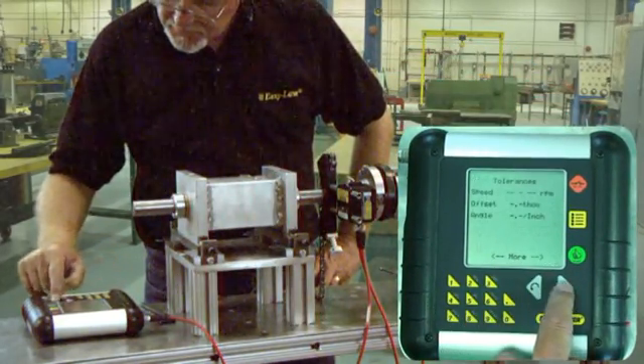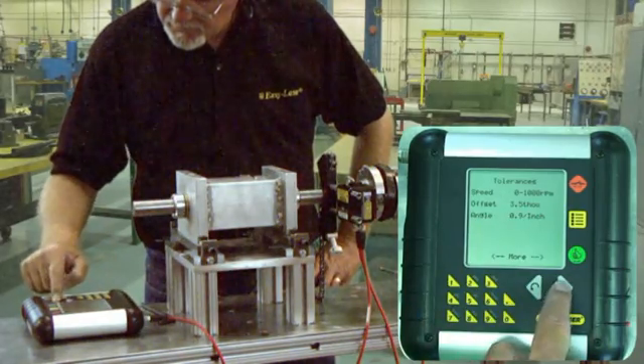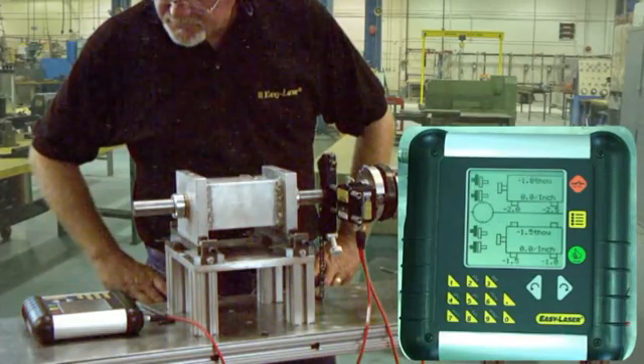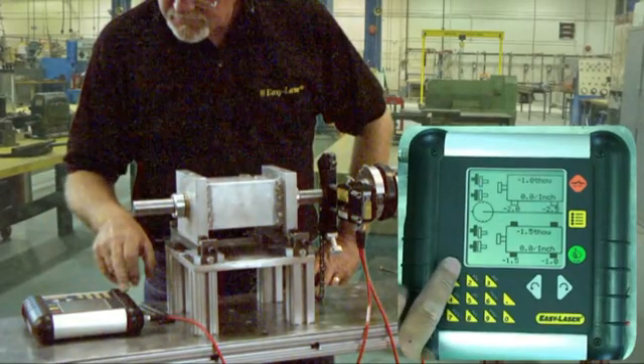Let's press button 4 and input our RPM. 0 to 1000 is the range we want. And as you can see here all the half couplings are black so we are within tolerance and the job is done.